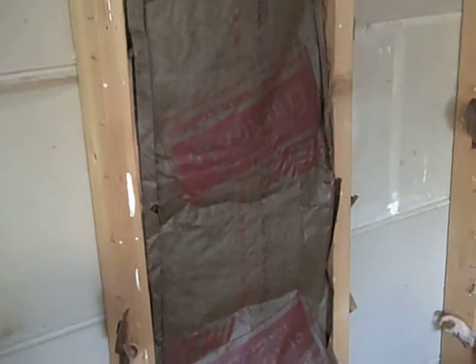I've got an interesting situation here — very common but interesting nonetheless. This is an exterior wall to a garage, and in the garage there is an outlet on the wall. When we pull off this piece of insulation, which I've pre-loosened, we can see the receptacle from the garage and the wire going up.